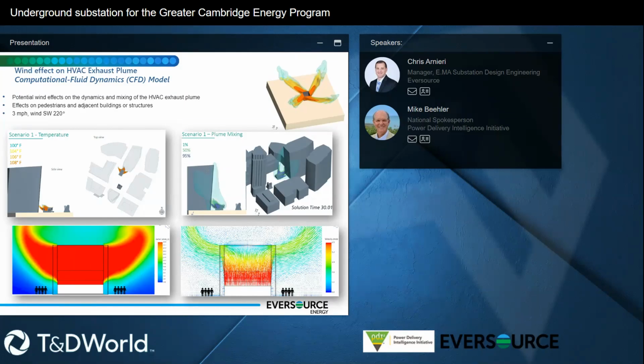Moving from the ventilation side, intake is pretty easy, we're just pulling air in. The only thing we were cognizant of with those high CFMs was the pull of air when someone's near the intake structure. But due to the design of the intake, we were able to pull from a higher level so the general public or the residential tower didn't see any impacts.